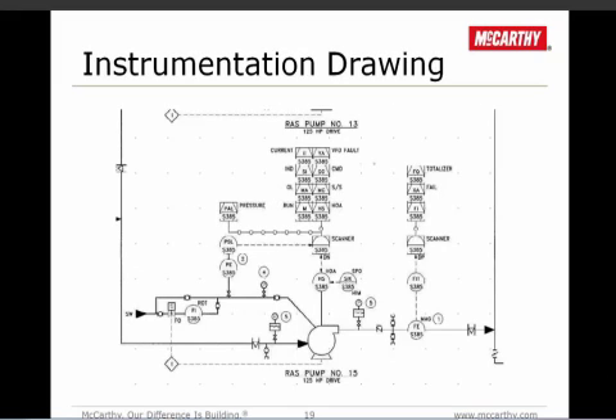The instrumentation drawings, a lot of times, show things like pressure gauges that weren't shown on the mechanical drawings. So we like to coordinate that so when we're doing our pipe takeoffs, we know where we need taps or connections for all our instrumentation. Make sure that all the items that are identified on the P&IDs are actually purchased and included in the list. Integrating and coordinating all these drawings as part of our startup plans helps us to understand what we're building, what's coming up, and the proper procedure for checkout and installation.